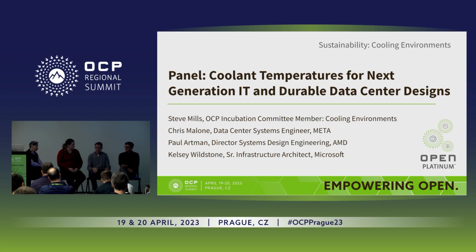Yeah, as you look at this, what you're seeing is that the dominant thermal resistance is the package. In traditional air cooling, the heatsink was for performance, and you really didn't think about the packaging too much. As we look at the bottleneck being the package, this is where you start looking at how thin you're making your die, and what kind of enhancement on thermal properties you're doing at the IHS, which is really the integrated heat spreader on top. It makes the chip consumable and very resilient, but it's another thermal resistance. So how we get thermal resistance down in the packaging is something we have to look at for sure.